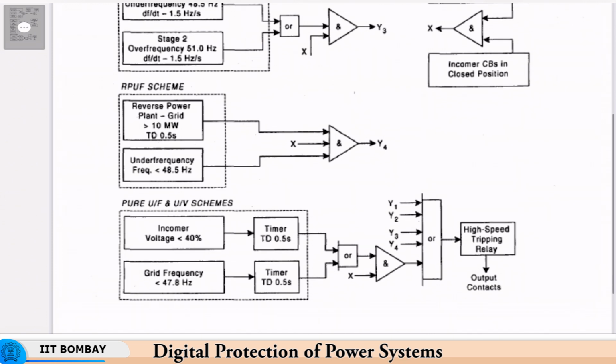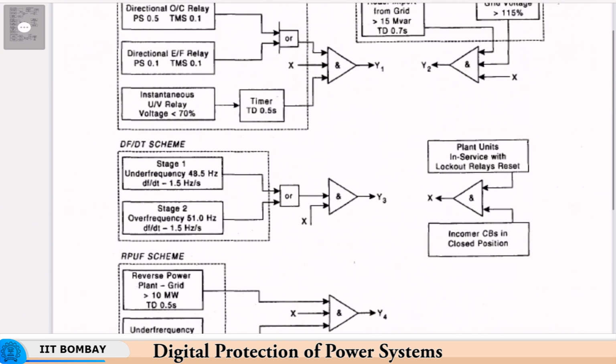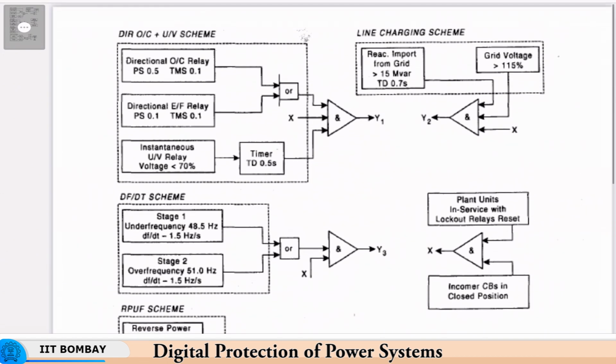issued. And sometimes, as we said, the load generation balance may not be disturbed so much. So to account for that, there are pure under frequency and pure under voltage schemes. So this is the islanding scheme which was used in actual practice.